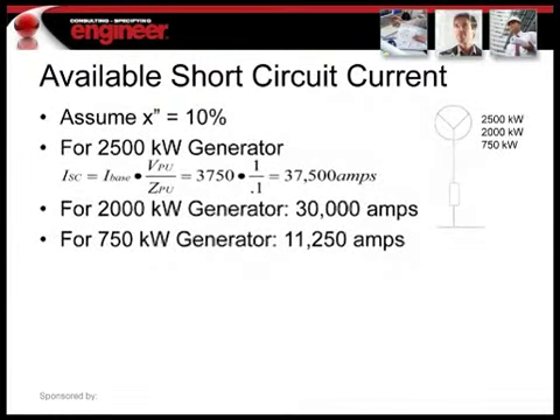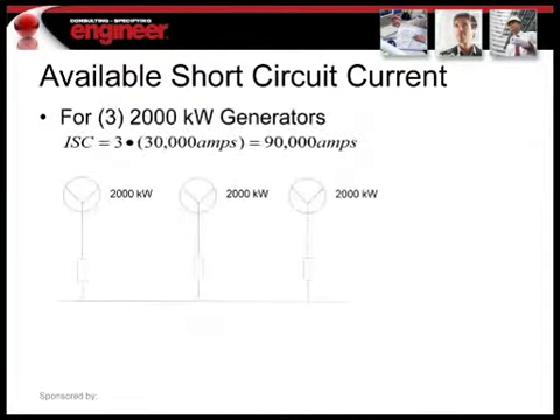And then this calculation represents something that Jim showed us already, which relates to the available fault current from a generator. I used a transient reactance of 10%, but there are actual values published by the manufacturers, as Jim noted, and those are the values that should be used. Again, this shows you that when you have a single generator, the available fault current drops considerably from that which is available from a utility transformer, and that needs to be considered when you're selectively coordinating and choosing your transfer switches. This is a configuration that has 3 generators in parallel, and again your available fault current is multiplied by 3. This is something you might find in a relatively large hospital where you're not only providing power for the essential branch, but also optional standby power for many other loads in the hospital as required by the owner.